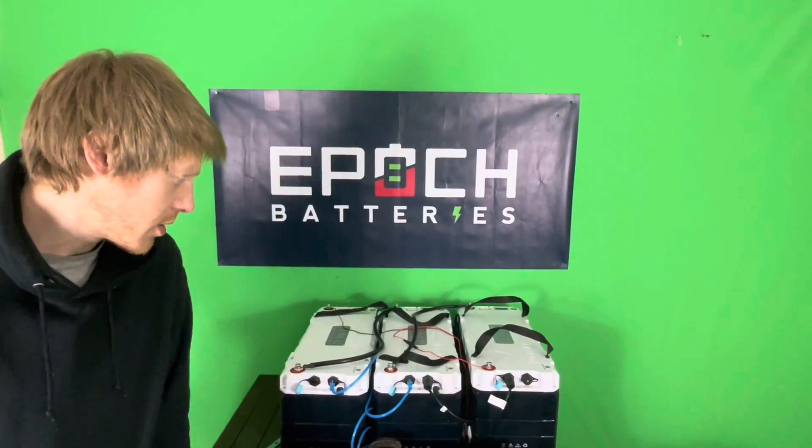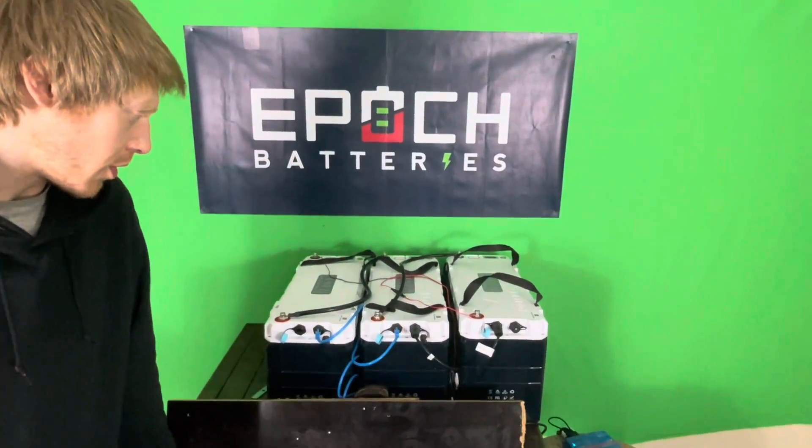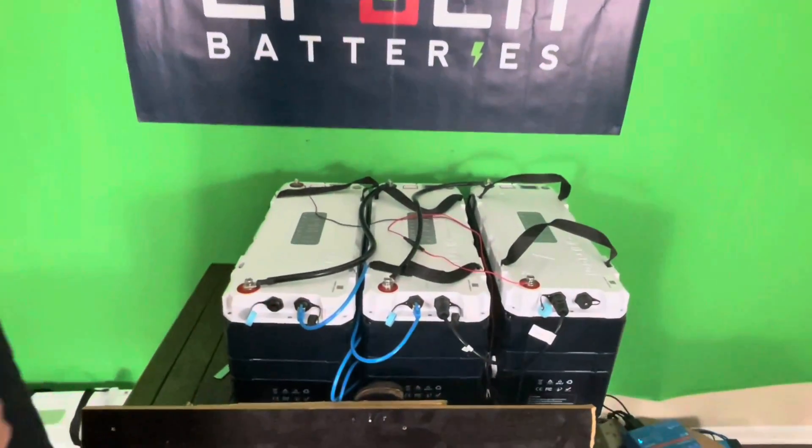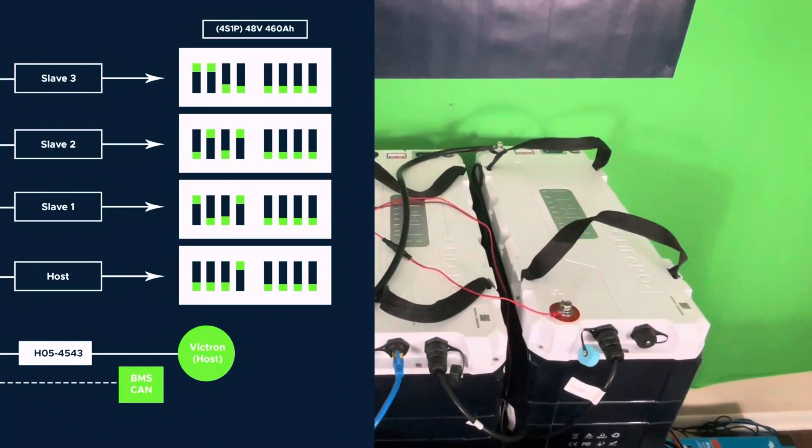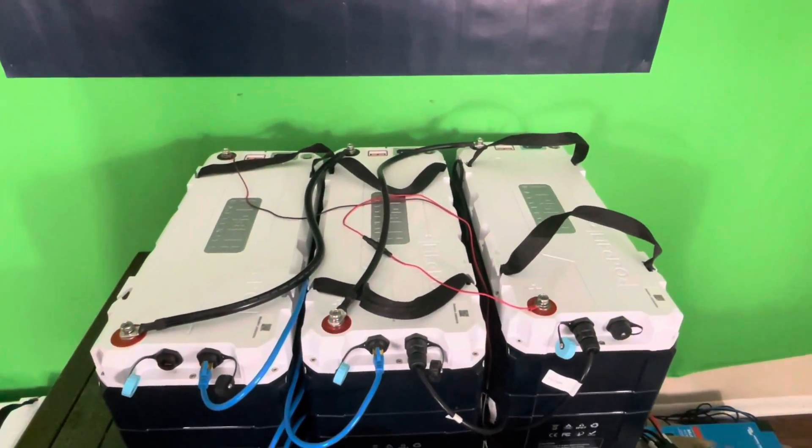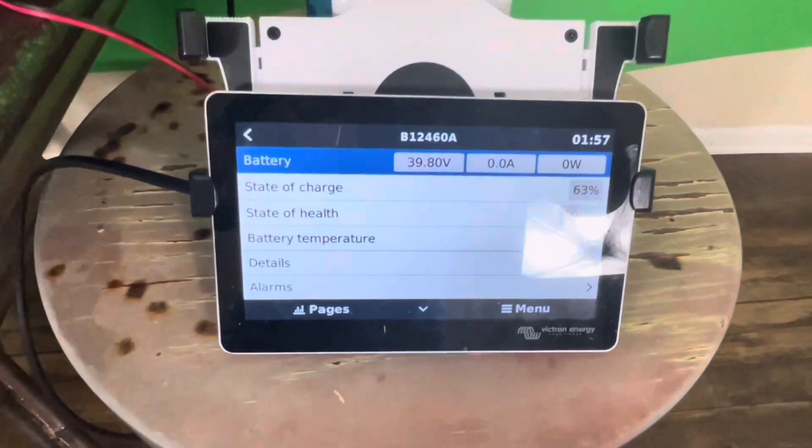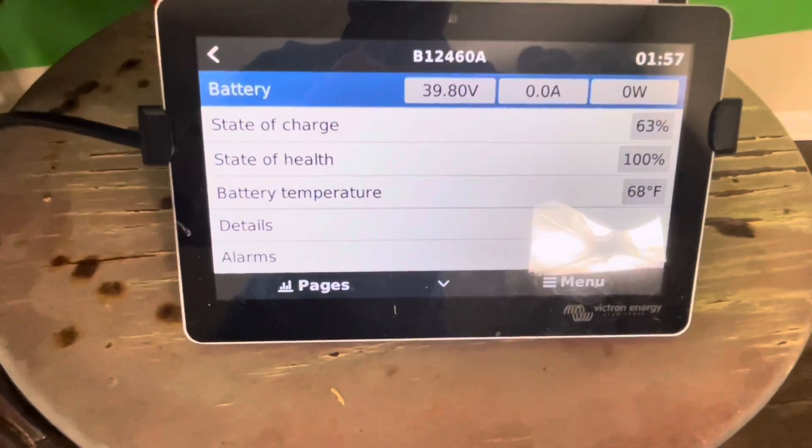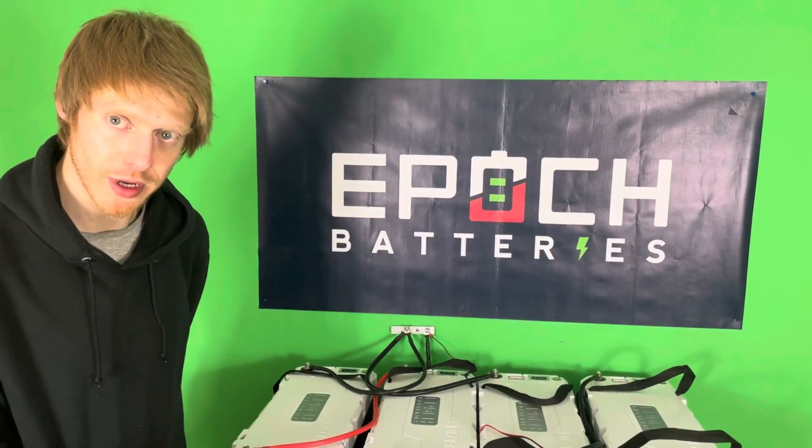Alright, now as we work our way back, we have a 4S1P configuration, so all these are going to be in series. Dip switch settings as you can see on the screen here, and we can verify by looking over at the Cerbo and we have a 48-volt battery, so 460 amp-hours. So that's all for this configuration and now on to the next.